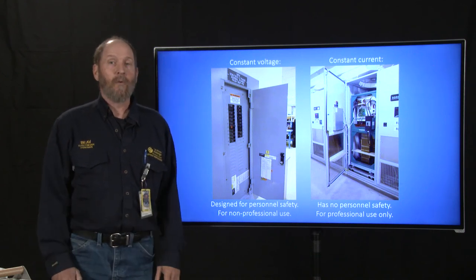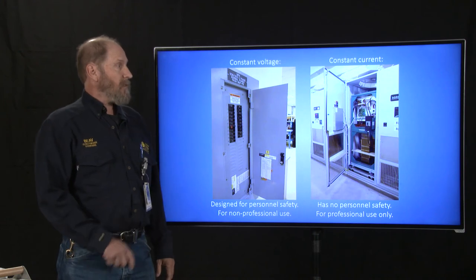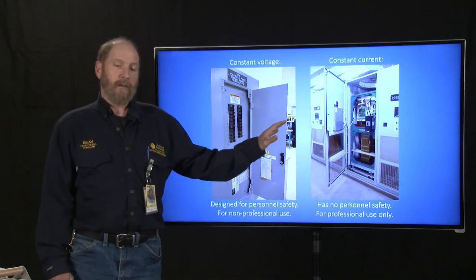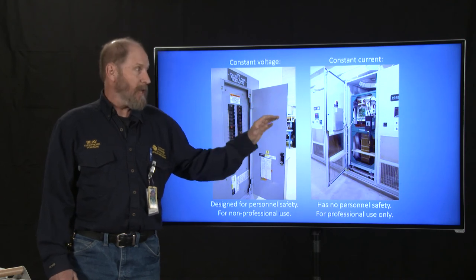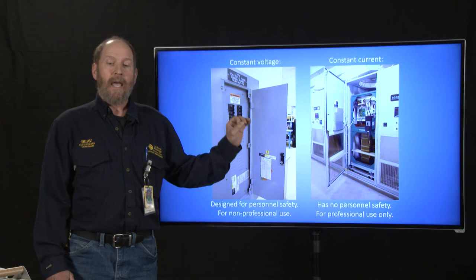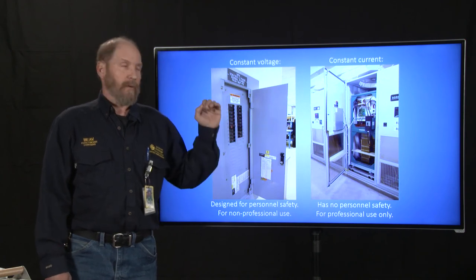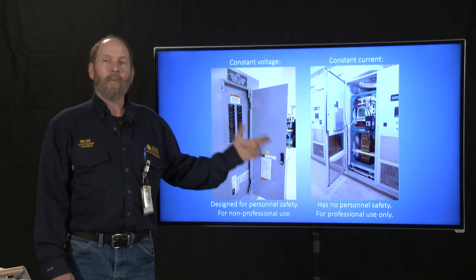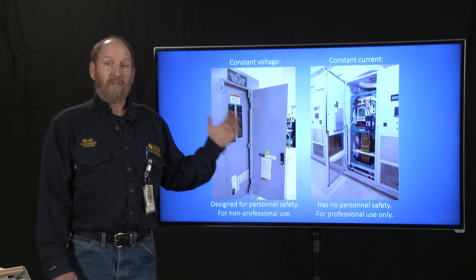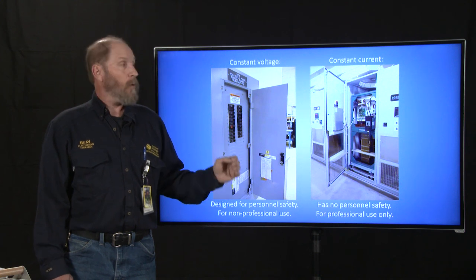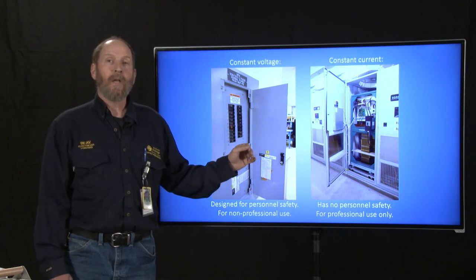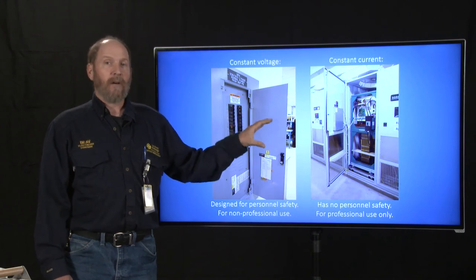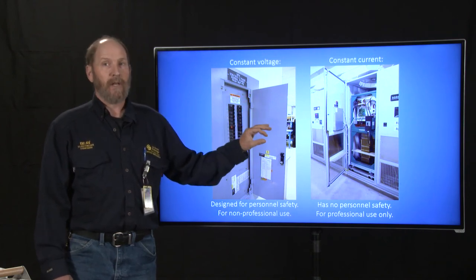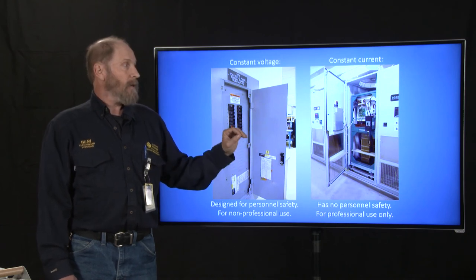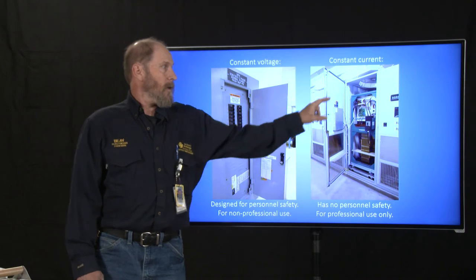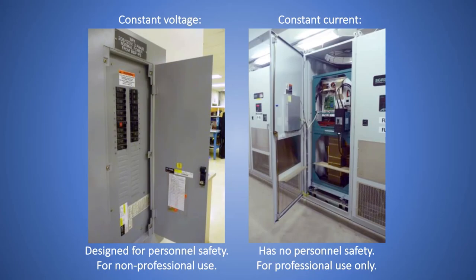It's for professional use only. And this system is designed to keep running and keep the lights on when a plane is on short final and it does not want to shut down. So if an electrician gets tangled up in it, if an equipment operator cuts into the wires, or if it starts something on fire, it doesn't care. The only reason a constant current system will shut down is because it thinks it's going to hurt itself. It's going to go beyond its parameters and burn itself up. Then it'll shut down. Otherwise, it doesn't care. So this, the constant current regulator, is the monster below that we were talking about.